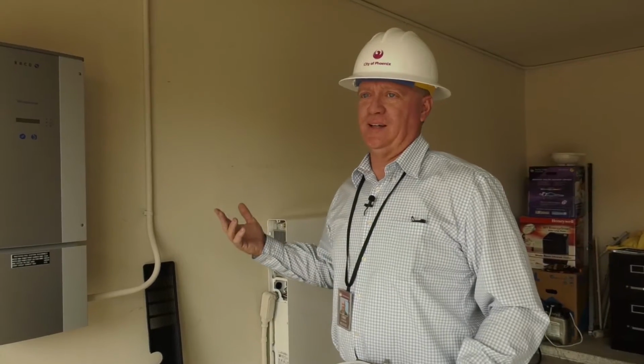One of the things, if you're not familiar with solar systems, a lot of people that go over, first thing you do, they flip off the main breaker to the panel. Now it's dead, there's no electricity. Well, with solar, if the sun's out and there's daylight, it's making electricity. So you have to understand that there's different directions the power can come from. So by understanding how the basic technology works, you can protect yourself.